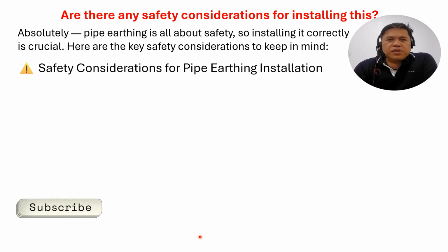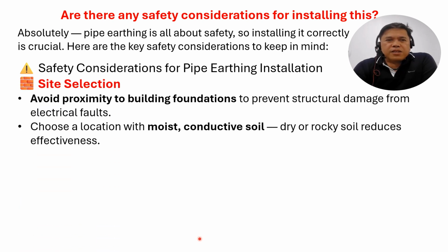Safety consideration for pipe earthing installation during site selection and installation: avoid proximity to building foundations to prevent structural damage from electrical fault. Number two, choose a location with moist, conductive soil - dry or rocky soil reduces effectiveness. Remember this when you do the inspection or the construction, verify and check all of this scenario.